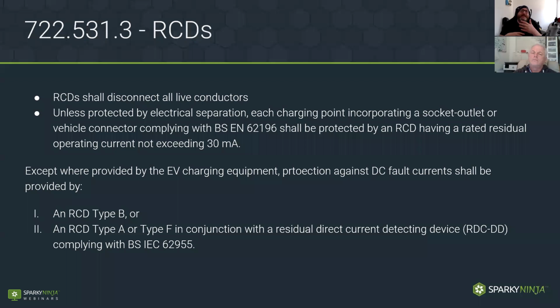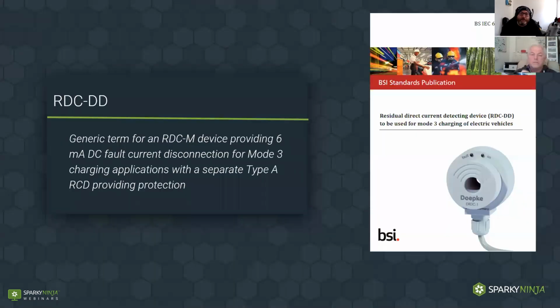Okay, it's a detecting device for residual current. And what that kind of does, there's a standard for it, which I've obtained, read, and I need to read again. It kind of supports, type A obviously does up to 6 milliamp pulsating DC. This kind of gives it a backup support. Yeah, it kind of supports type A RCDs, okay, for 6 milliamp fault currents for DC. So again, manufacturers will use a variety of options. If you use charging points that have internal protection, then that decision-making process should have been made for you.